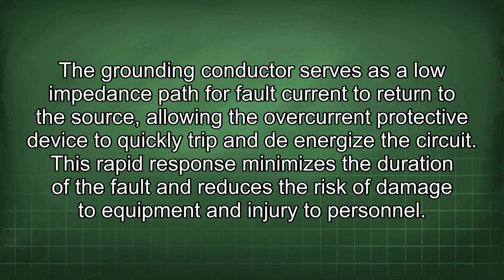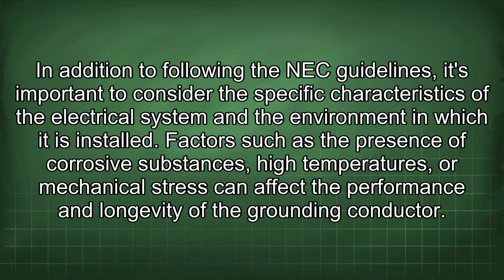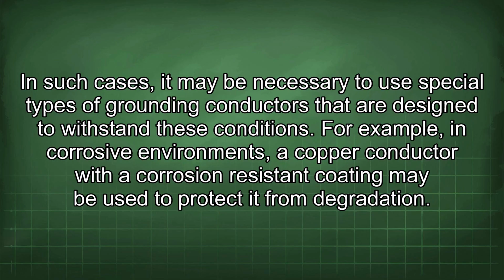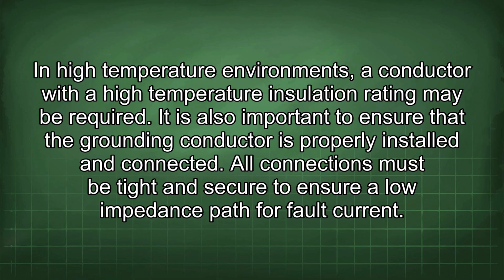This rapid response minimizes the duration of the fault and reduces the risk of damage to equipment and injury to personnel. In addition to following the NEC guidelines, it's important to consider the specific characteristics of the electrical system and the environment in which it is installed. Factors such as the presence of corrosive substances, high temperatures, or mechanical stress could affect the performance and longevity of the grounding conductor. In such cases, it may be necessary to use special types of grounding conductors that are designed to withstand these conditions. For example, in corrosive environments, a copper conductor with a corrosion-resistant coating may be used to protect it from degradation. In high-temperature environments, a conductor with a high-temperature insulation rating may be required.